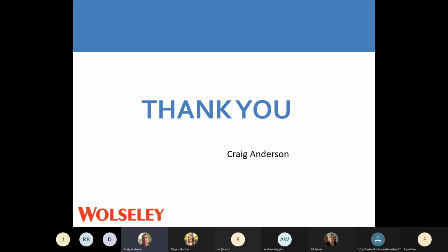Dropping off an air conditioner to a branch the next day saying it doesn't run, I want a good one, just creates a lot of havoc for the branch and the TSAs. So yes, like I said, startup documentation is 100%. Amperage, pressures, anything you can give us gives us a better, smoother go-through. But if you can talk to a TSA, that is the best way to start.